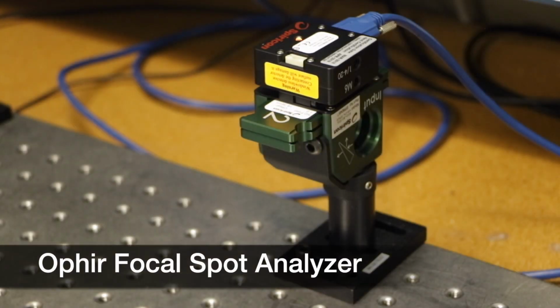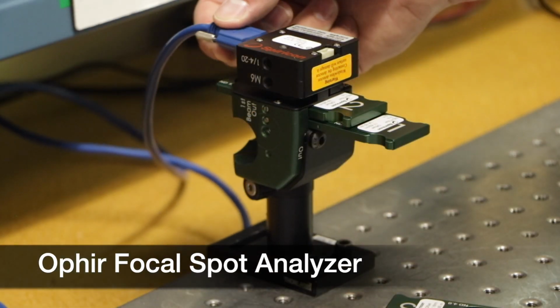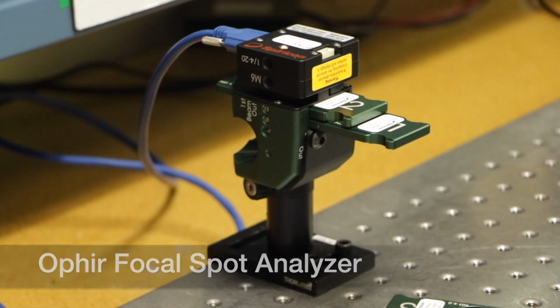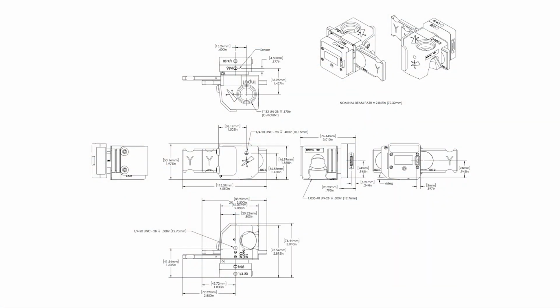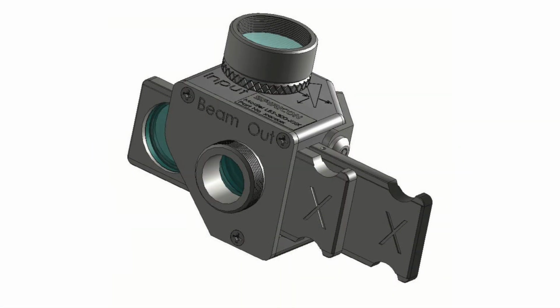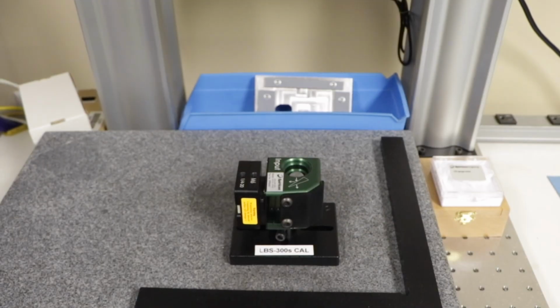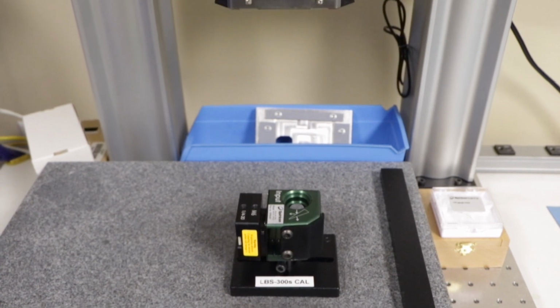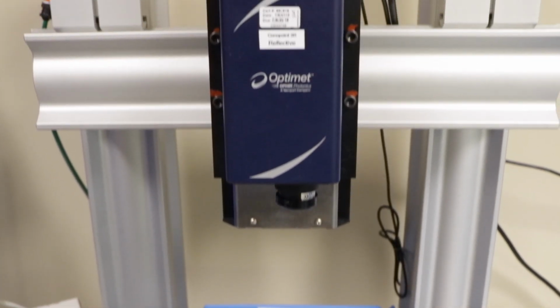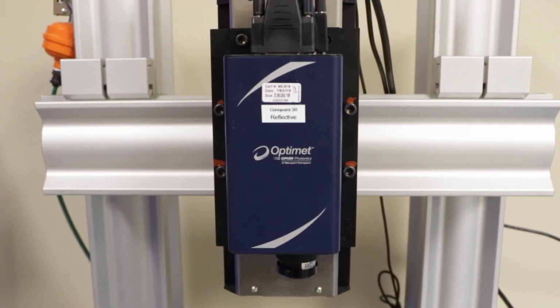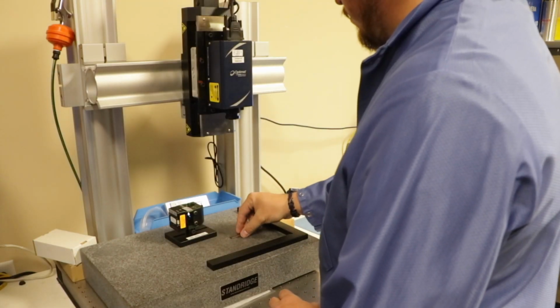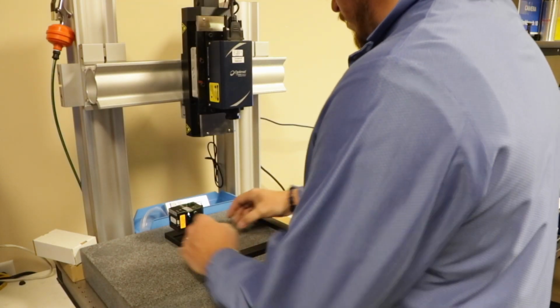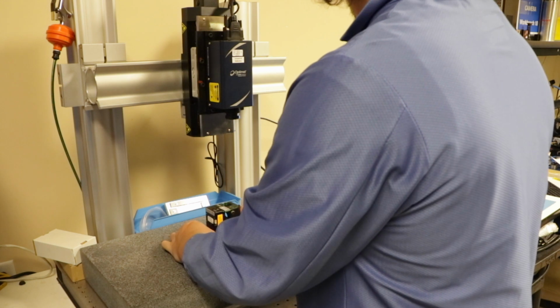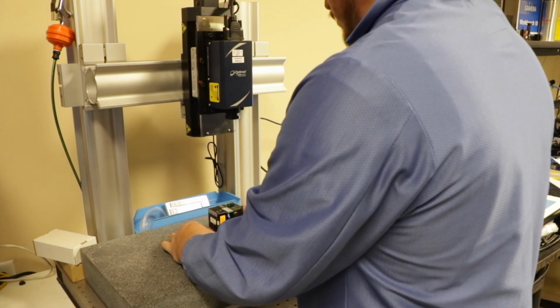The Ophir Focal Spot Analyzer allows users to understand exactly where along the optical path the measurement is being made, as referenced from the front surface of the device's input aperture with plus or minus 50 micron accuracy. This NIST traceable distance is measured by employing conoscopic holography, as provided by the ConoPoint 10HD from Optimet, a non-contact laser-based distance measurement device that provides world-class resolution and unparalleled accuracy.